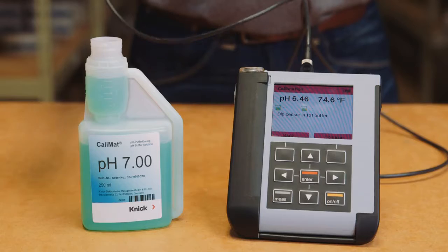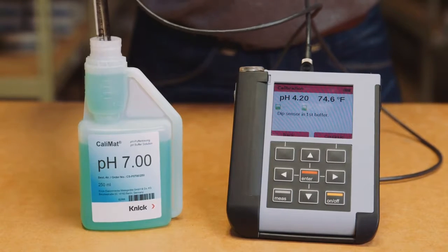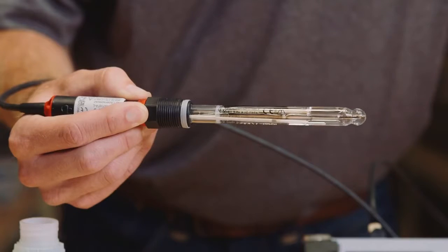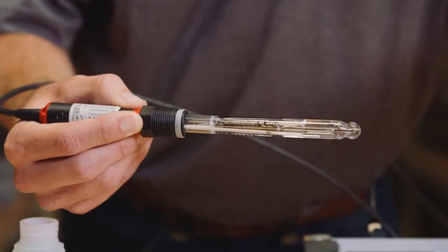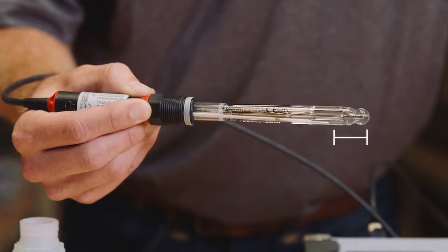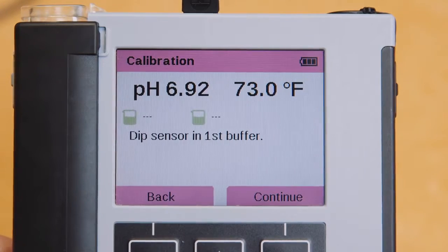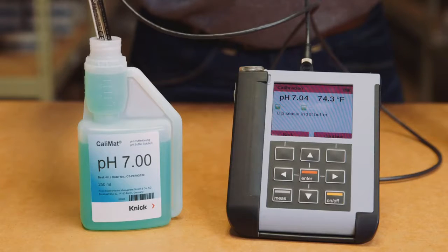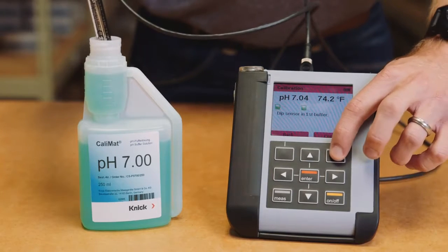To begin the process, dip the sensor in the first buffer solution and stir lightly. The junction on the sensor needs to be fully immersed in the buffer, covering about 1 inch of the sensor. It's also very important to let the values on the top of your Portavo screen stabilize. Once the values have stabilized, press the Continue button.